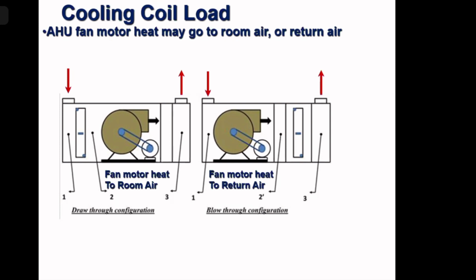So, the left one, what is happening? The air is first cooled. So, cooling coil is done, cooling is done. And the air handling unit fan is after that. So after the cooling is done, my fan motor gives it. So that will not come in the return air. That will straight away go to the room air, that heat of the motor. So that will be added to the effective room sensible heat. It's called draw-through configuration of air handling unit. Draw-through means it draws air through the cooling coil.